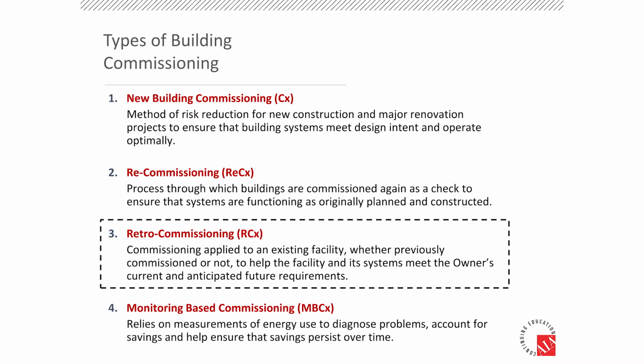Retro-commissioning is where it's important for us in these old buildings, because after so many years, we change the footprint and the layout of our buildings. A restaurant is now a retail space, or a casino, or we put in a separate walled-up space where it was all open. We're changing the footprint, we're changing the use, we're changing how the systems need to perform. We build on, add on, now we need to add a new central plant, tie those together or not, all of these things. So we're trying to retro-commission the old systems to the new usage. And then typically after that, you go into monitoring-based commissioning to try to maintain.